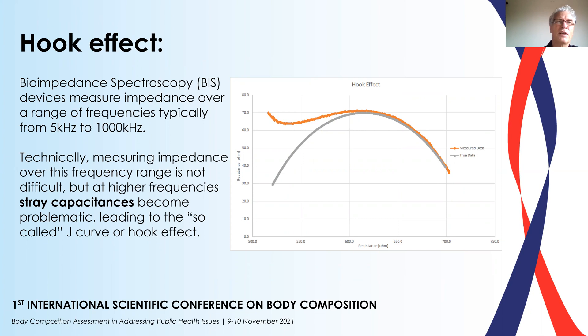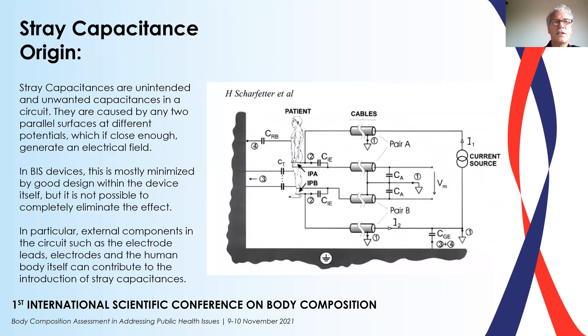However, bioimpedance spectroscopy devices can measure impedance over a range of frequencies, and technically measuring impedance over these frequencies is not difficult, but at higher frequencies, stray capacitances become problematic, leading to the so-called J-curve or hook effect. Stray capacitances are unintended and unwanted capacitances in the circuit, caused by any two parallel surfaces at different potentials which, if close enough, generate an electric field. In BIS devices, this is mostly minimised by good design within the device itself, but it is not possible to completely eliminate the effect. In particular, external components such as the electrode leads, electrodes, and the human body itself can contribute to the introduction of stray capacitances.